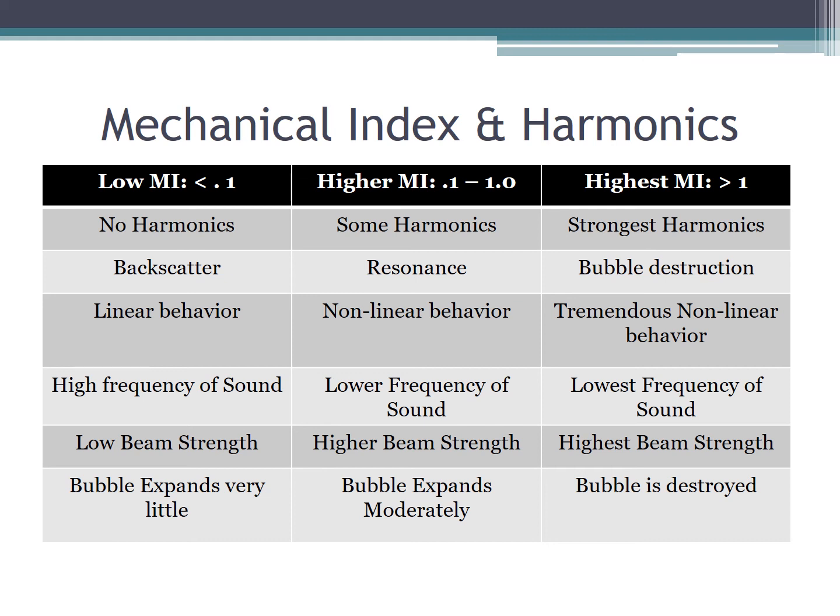Most likely with the low mechanical index, we're going to have a high frequency sound beam, which means that the beam is low strength, and the bubbles are really going to expand very little. So the low mechanical index does not help us with contrast harmonic imaging.